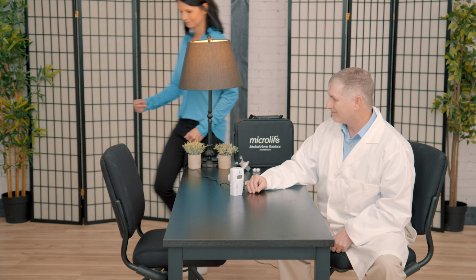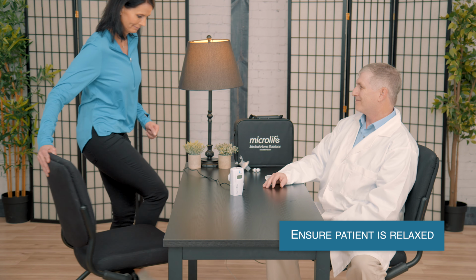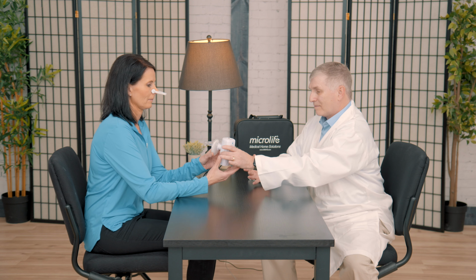When you're ready to use the device, ensure that the patient is relaxed in a comfortable seated or reclined position and has not consumed food, stimulants, or has exercised for at least 4 hours. To begin this process, place the nose clip on the patient's nose to close the nostrils, position the mouthpiece inside the patient's mouth, and make sure the patient maintains a good seal around the mouthpiece.